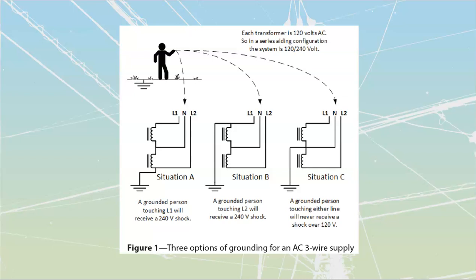All right, for the review over here, the purpose of grounding and bonding is to prevent fire and shock hazards. And inside of the Canadian Electrical Code, one of the big things that we want to do is prevent electrical shock to humans. So Rule 2-104 tells us that a human should not be exposed inside of a dwelling unit to more than 150 volts above ground. And over here we see that we want to use 120/240-volt systems.